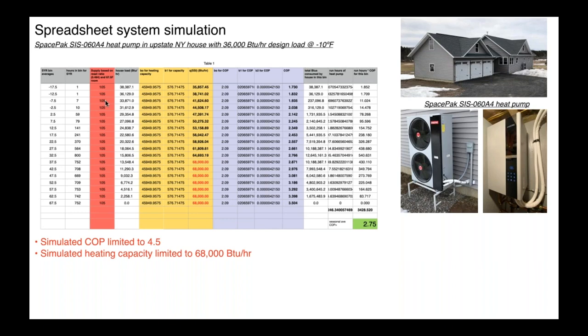And in the spreadsheet you're looking at here, you'll see I kept the water temperature all at 105 degrees because of how the controls were set up. Basically, the buffer tank temperature was what turned the heat pump on and off. And the way it was, and still is, configured, when the buffer tank dropped to 100 degrees, the heat pump turned on. When it got up to 110, the heat pump shut off. So our average temperature that the heat pump was operating at was 105. And again, we limited COP to 4.5. We limited capacity to 68,000. And we're getting a seasonal weighted average coefficient of performance of 2.75, a little lower.